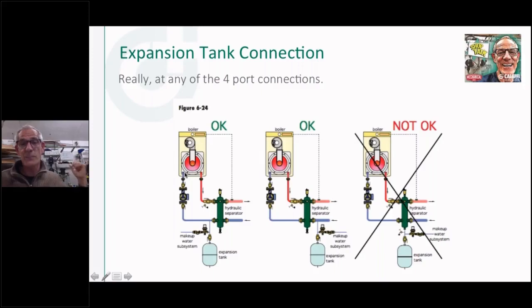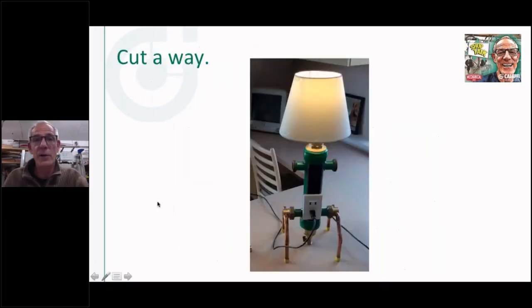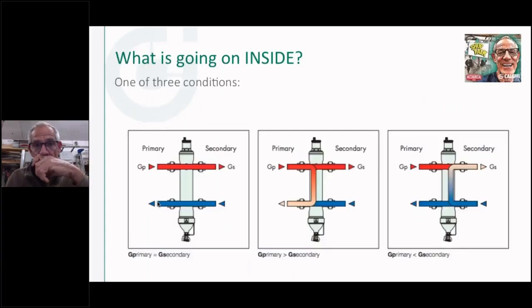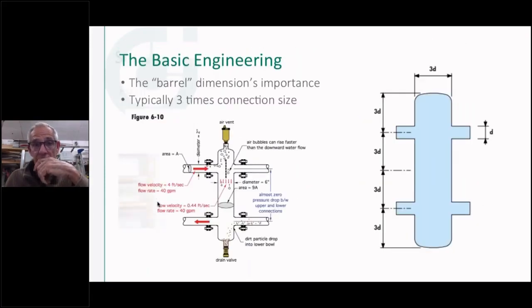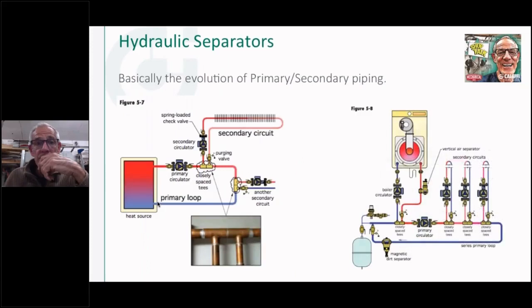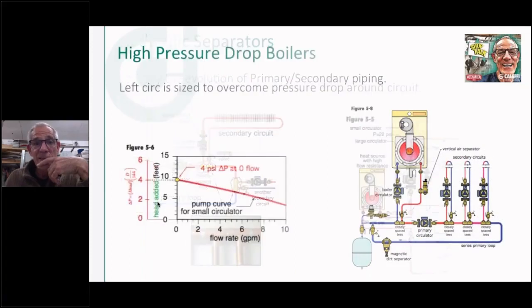On the back side of this display, I did a pumping away, and I'll show you what happens to an expansion tank when you pump at an expansion tank, and it's going to blow your mind what happens. So we want this circulator delta P, the pressure differential that establishes. I'll probably go back to that early drawing and show you that better, since I think we put the numbers on that. Bear with me here for a second. I forgot exactly where it was.